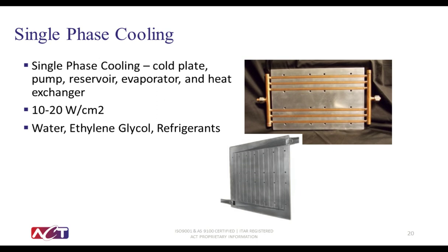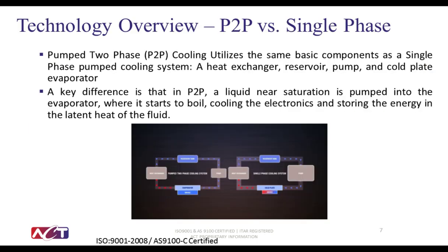To examine the benefits of pumped two-phase cooling, it might be beneficial to review the basics of traditional pumped liquid single-phase cooling. In these systems, a chilled liquid is pumped through tubing or a manifold that is in direct contact with the heat source. The main components are the cold plate, a pump, a liquid reservoir, the evaporator or heat source, and the heat exchanger or chiller. These systems can typically dissipate 10 to 20 watts per centimeter squared, but are often defined by the size of the pump. Working fluids are commonly water, ethylene glycol mixtures, or refrigerants.